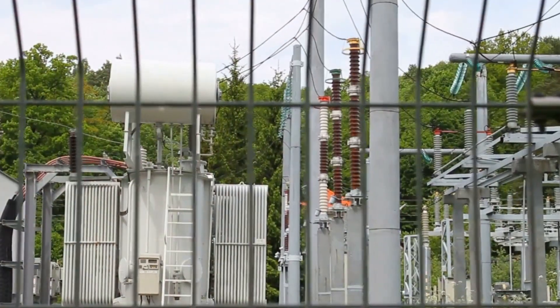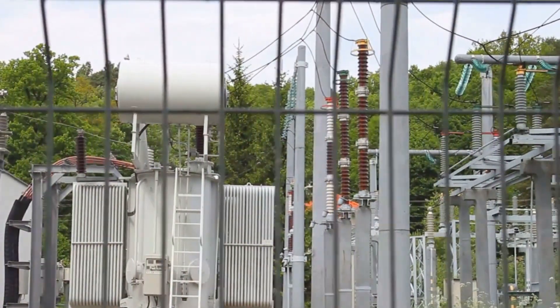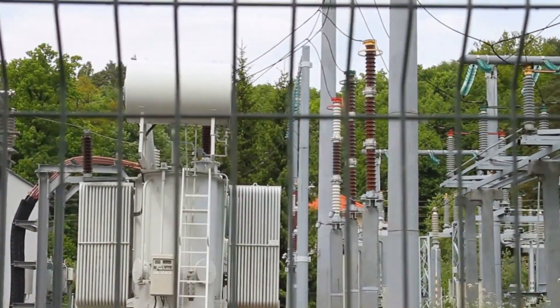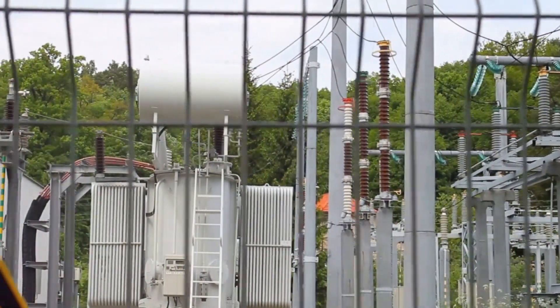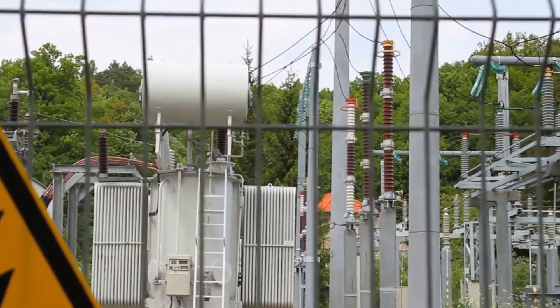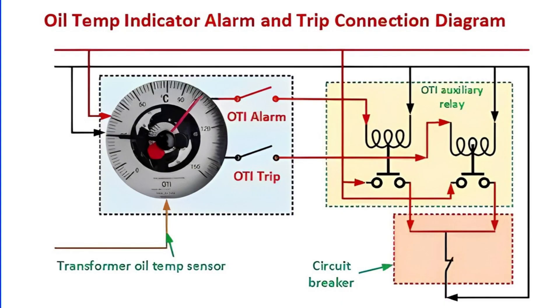Moving on to mechanical protection, which involves the oil temperature trip relay, winding temperature trip relay, pressure relief valve, and Buchholz relay. Starting with the oil temperature trip relay: this device monitors the oil temperature, acting swiftly when it detects an increase beyond a predetermined value, typically a sign of an internal fault.